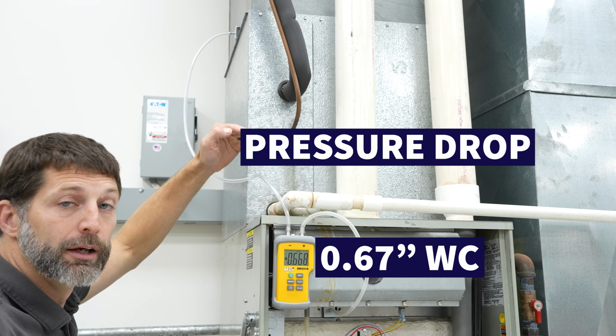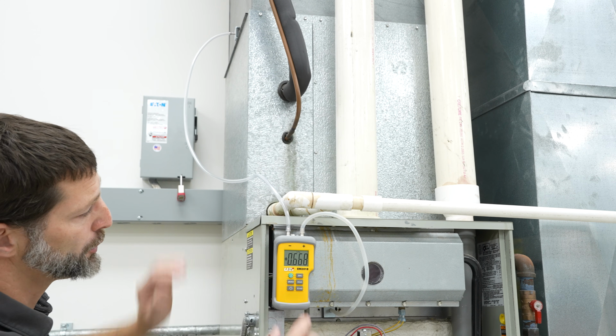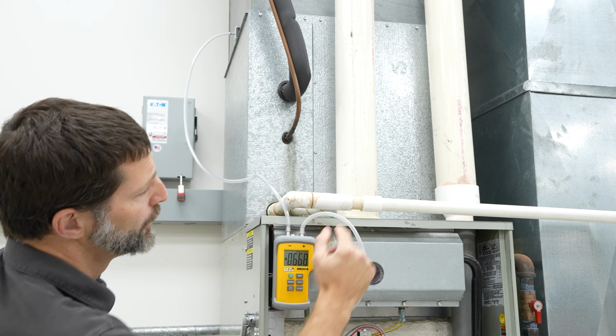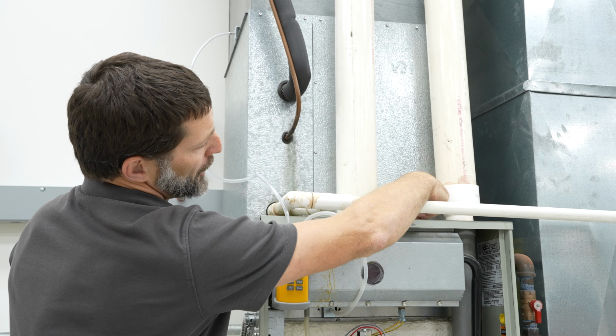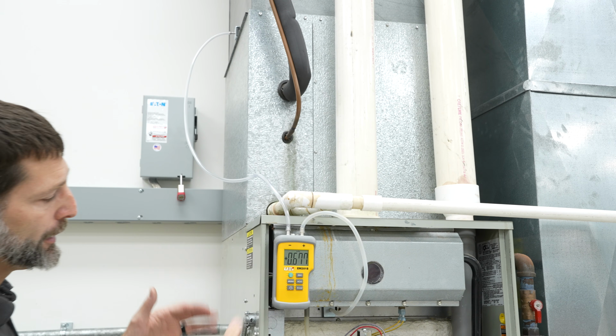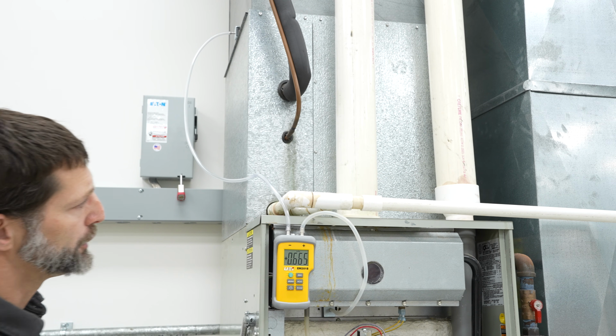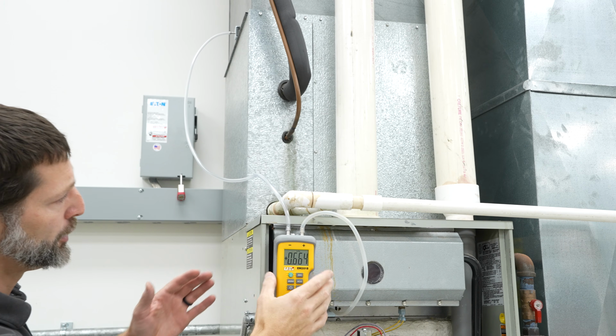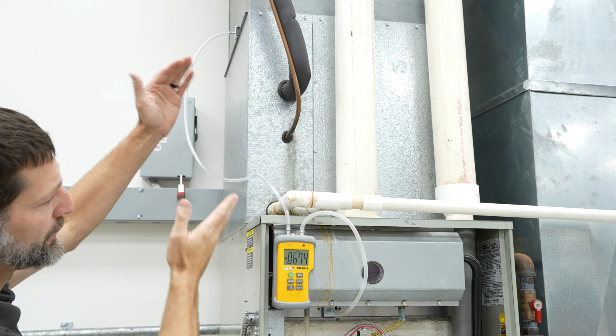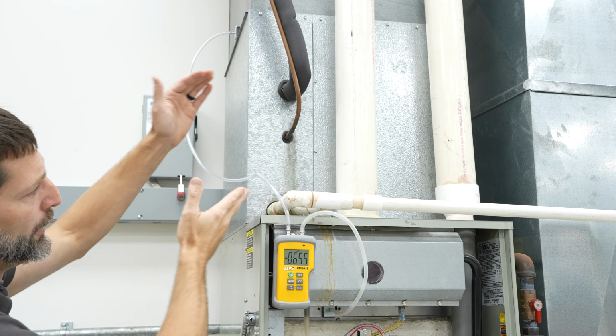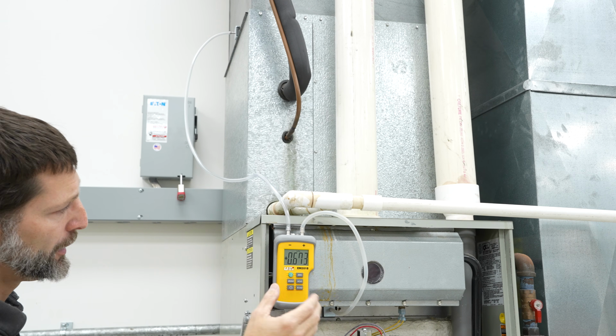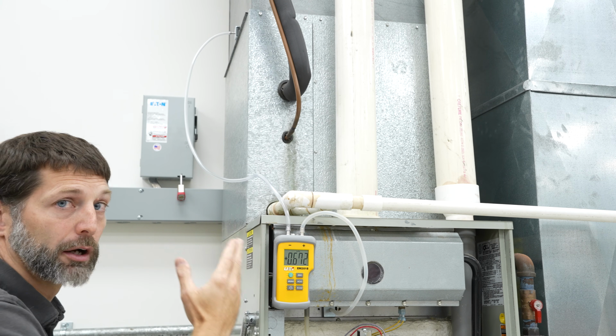significantly high. So we know we have a problem with this, but you can also compare this to the static pressure of the model coil at the selected airflow. You can use the manufacturer's literature to determine if you have a higher static pressure drop across this coil than what the manufacturer chart says, and that means that the underside is clogged with dust.